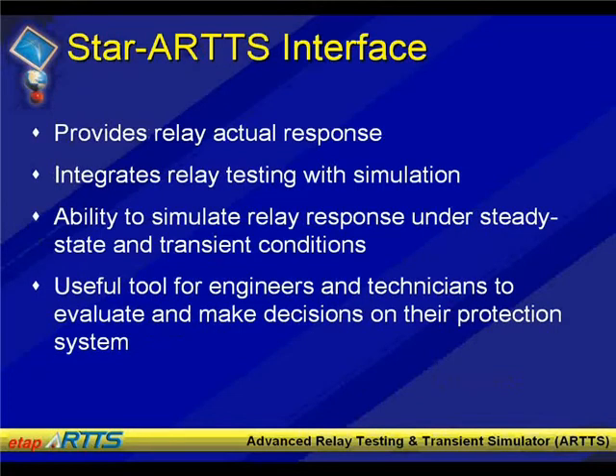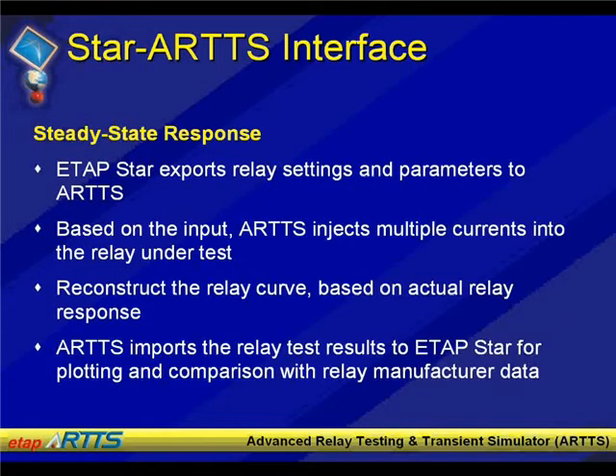A little bit more about the Star-ARTTS interface before we go to the program: this is a bridge between the two platforms that brings the relay testing data and manufacturer relay data together and provides that in the relay testing environment. The idea is to provide testing and simulation of the relays. We talked about steady-state response — the first demonstration is exporting relay settings and parameters, including device settings, relay settings, and curves into the ARTS environment, then injecting current using the ARTS hardware to see the response, reconstructing the relay curve based on actual response, and bringing that information back into ETAP STAR for display against the manufacturer-published data.